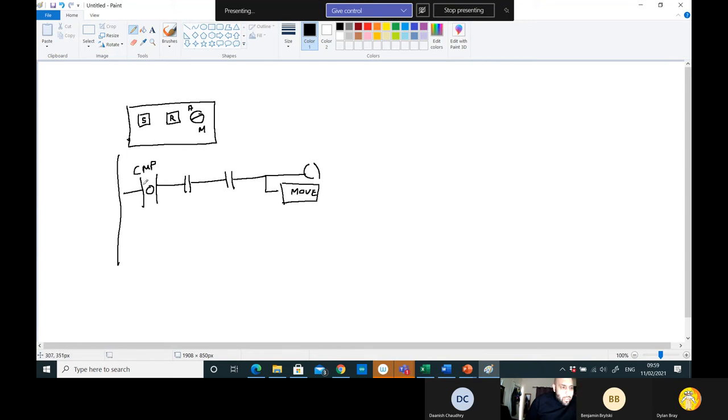This is like compare zero. This is stage zero, the first level. And then the next stage will be like compare 1, CMP1. So that will move to put 1 into a particular address location, MW, wherever it could be. And then that will compare that in any MW. If that one goes into there, that means it's ready to go to stage one. So compare one, stage one's there, then that will do whatever you want it to do. This is called sequential programming. It's the easiest way to program to go to different stages.